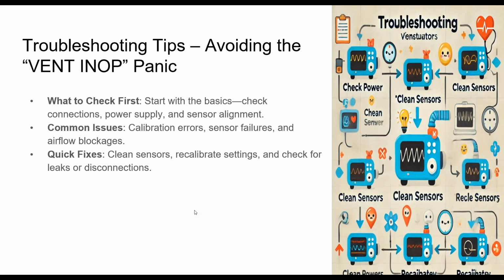So some of the quick fixes, and I call these quick fixes, are to recalibrate some of the settings. This is not something they would typically do with the patient on. You could clean the sensors. Again, not something you would do with a patient on, but checking for leaks or disconnections is a very quick fix for a lot of ventilator problems if you get called and everybody else hasn't found this problem yet. I have seen it go both ways, where a respiratory therapist has recapped a connection that I just checked, and it worked after that. We know then that it's kind of a faulty cap or faulty luer connection, but it goes the other way too. Biomeds might say, oh, you did all this?